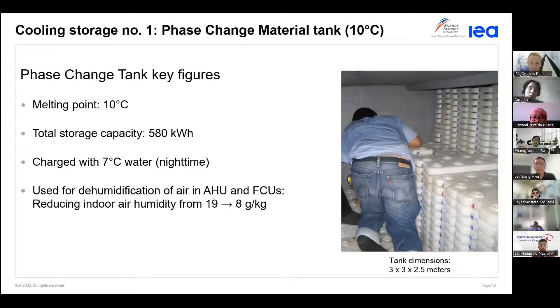So come morning, we can switch off the chiller, and in the daytime we only have to run a little circulation pump to push water through this tank. The ice packs melt and we get about 10-degree water out of the tank, which is good enough to do some dehumidification, so we run this water into the air handling units and the fan coil units.